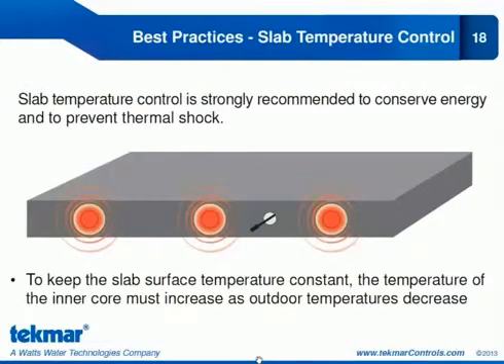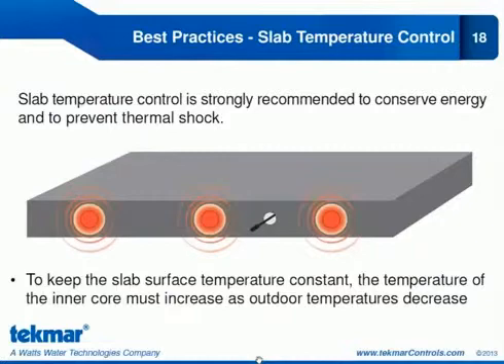Slab temperature control is another best practice associated with snow melting. We want slab temperature control to avoid wasting energy and to protect the slab. If the slab is heated too quickly and the temperature differential is too great, we are at risk of cracking from thermal shock. Effective control is essential to keep the slab surface temperature constant. The way we do that is by varying the temperature to the inner core in relation to outdoor temperature changes — if the outdoor temperature drops, we increase the inner core temperature to keep the slab surface temperature constant.